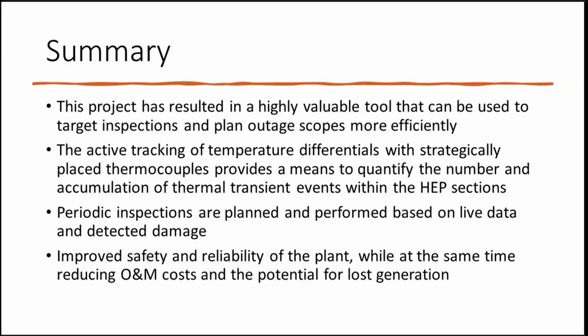So the very first iteration was we ran the representative transients and determined how much stress and strain we got from those and related that to damage as a simple lookup table. So that wasn't real time. What we've gotten to now is building out basically Green's functions related to that, more real time, tying the temperature and pressure to a direct stress and strain. And so that's certainly what we're implementing for Duke.